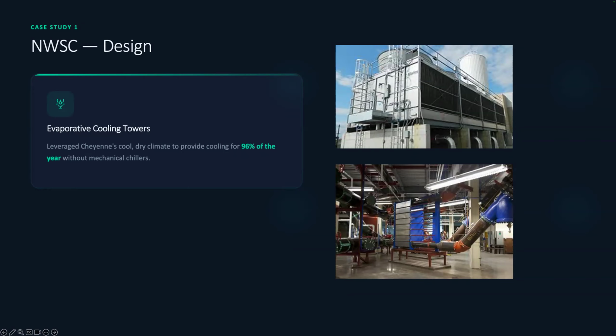We also drove the architects crazy because we said we wanted 45-degree angles for piping. So that's not a tilted picture. It really is 45 degrees, and that eliminates a lot of drag in the piping. 90-degree elbows create turbulence and drag. So everywhere we could, we put in 45-degree piping locations.